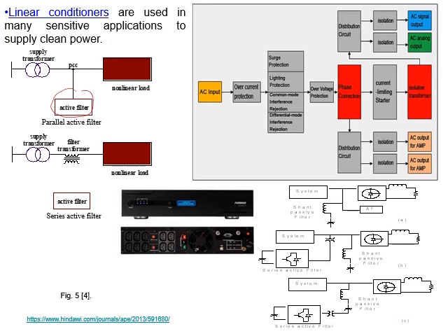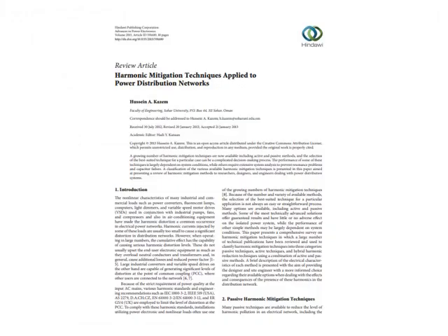Active filter, as an example. By the way, there is active filter, there is passive filter, there are different types. And there is hybrid, which contains active and passive. And the active filter could be parallel, as you can see here, connected to the same point, PCC, point of common coupling, with the load, or it can be connected in series through a transformer, as you can see.